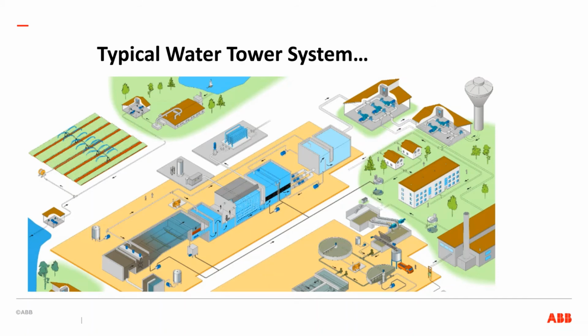So when you're filling the water tower, the pipe is flowing up. When you're draining out of it, the water's flowing down. So what you do is you increase the pressure in your system so that your water flows back up into the water tower. Again, with constant pressure, that increases the pressure in your whole system, which means if you have a 1 millimeter leak and it's at 60 psi, now you're filling the water tower, it's at 90 psi, you're wasting more water. So that's one of the reasons we're out there promoting a little bit about getting away from water towers. Next slide, please.